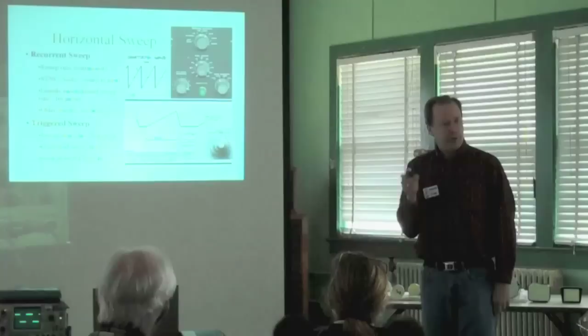There's like a 304 that was like that. Of course, the later ones all became trigger sweep, and that's really where we are now. And most of the scopes here now are called trigger sweep scopes. The difference is we're still generating a sawtooth wave to sweep the beam across the screen and retrace it back. But it's not really free running. It's going to sit there waiting with the beam over on this side until something kicks it off. And what kicks it off is something called a trigger.